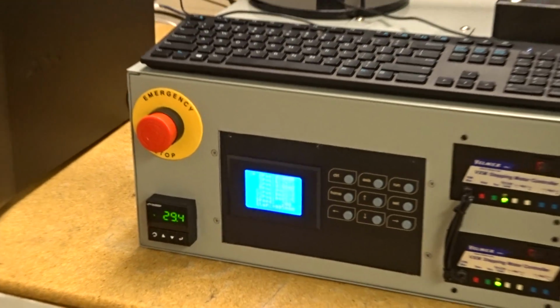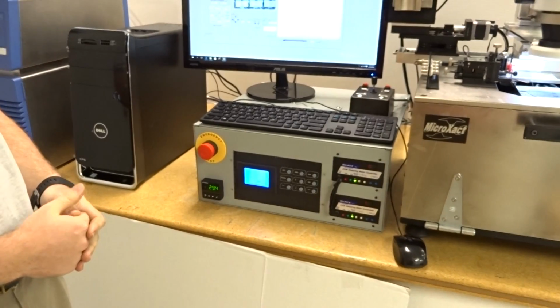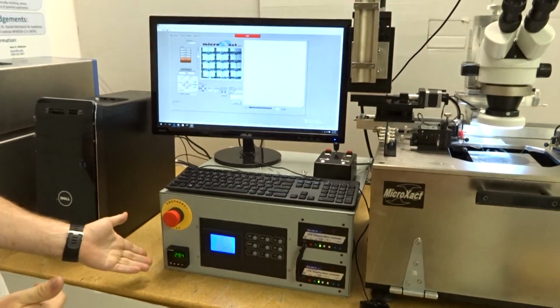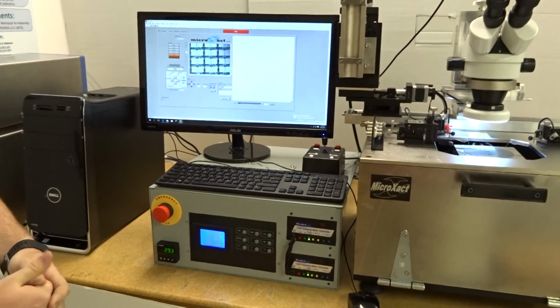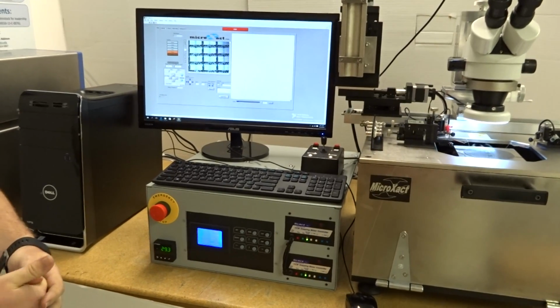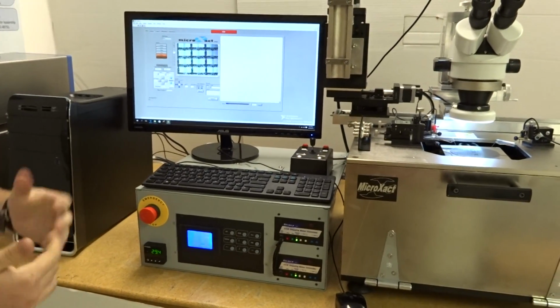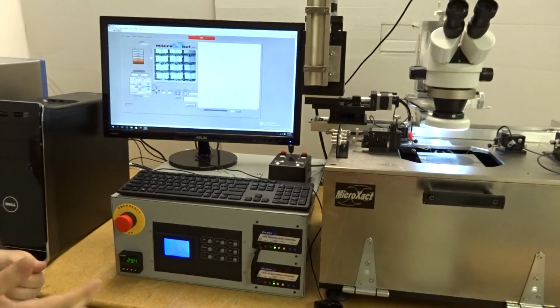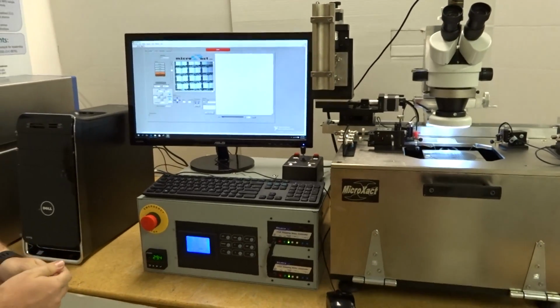We also have on this system a temperature controller that's able to control between 5 degrees centigrade up to 80 degrees centigrade. We have other controllers that can go into much lower areas if you're looking for a vacuum system, or up to 600 centigrade on the other side.